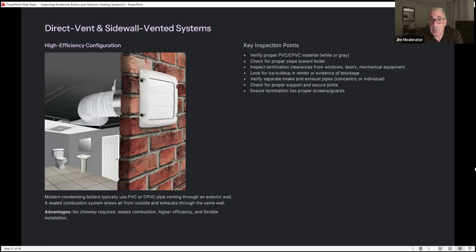Check for proper slope towards the boiler. Inspect termination clearances from windows, doors, and mechanical equipment. Look for ice buildup in the winter or evidence of blockage. Verify separate intake and exhaust pipes, and check for proper support and secure joints. Ensure termination has proper screens and guards. Also check for proper height outside. So these are a couple of things that you have to look for.